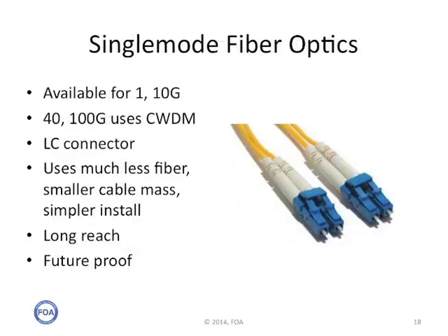Single-mode fiber has practically unlimited bandwidth and distance capability when used in data centers. Unlike the parallel 10 gig channels used with multi-mode fiber, single-mode fiber uses coarse wavelength division multiplexing to transmit multiple channels over one pair of fibers at different wavelengths. Thus, 100 gig is achieved using 4 25 gig wavelengths over only 2 fibers, greatly simplifying fiber installation and management.